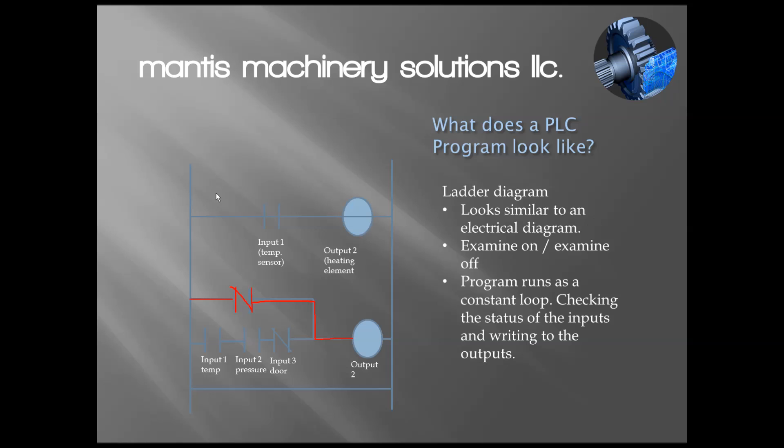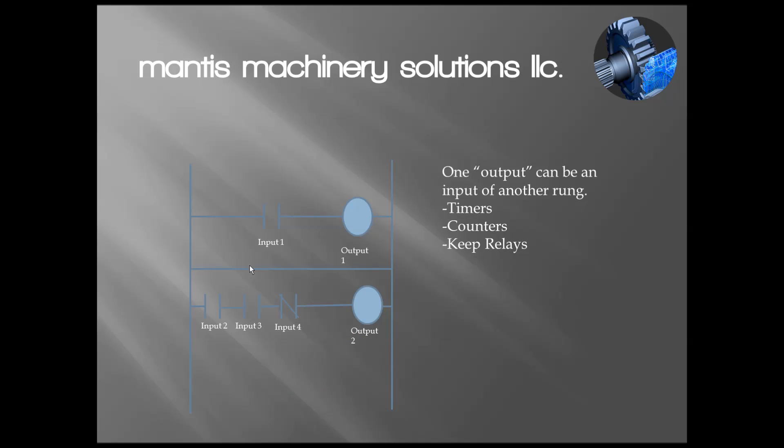This was ladder logic. There's one more thing I'd like to mention - timers, counters, and keep relays. Basically they are software. For example, you could have a timer that is not a physical device, it's built into the software, into the PLC. Its job is to time. Say output number three was some sort of a lubrication pump. I have input number five, maybe that's a push button switch that tells it we need to lubricate the axis. We know the pump, if it runs for 10 seconds, that's enough oil. I would set this timer in the software for 10 seconds, and then once it's expired, it opens up the path and the pump turns off.